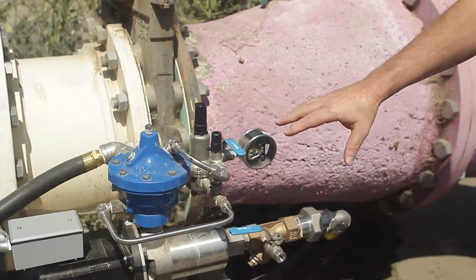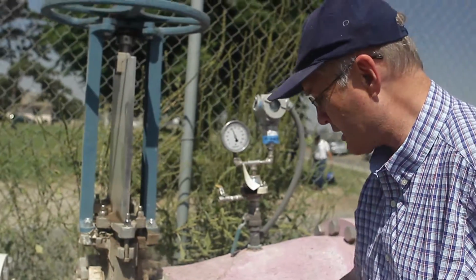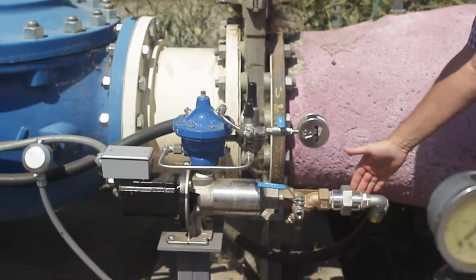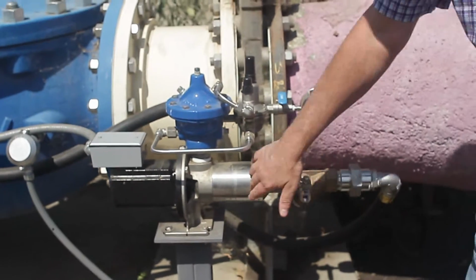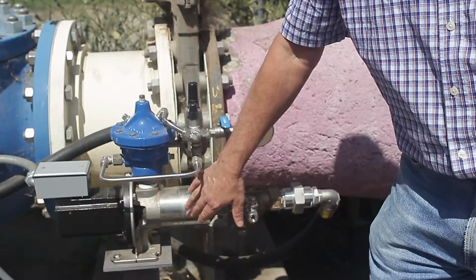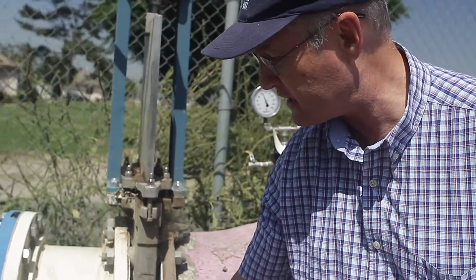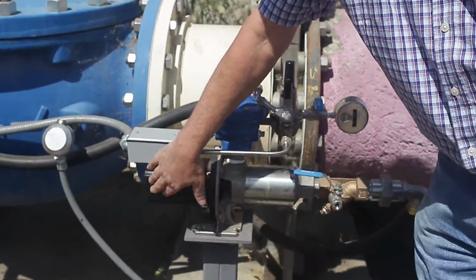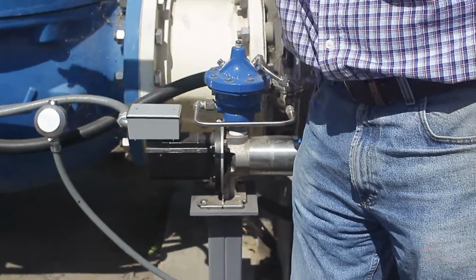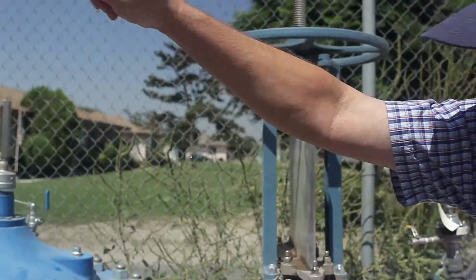Okay, I'm Roger Lay with Clay Valve, Technical Product Specialist. Jeff Varney just introduced the main valve and the generator. I'll just touch on the generator specifics. As Jeff said, the inlet pressure is coming up from the inlet body tapping through a filter, through the generator, which, as you might notice, is nothing more than a pump in reverse, and then the generator itself sending the power output to the panel over on the end here.